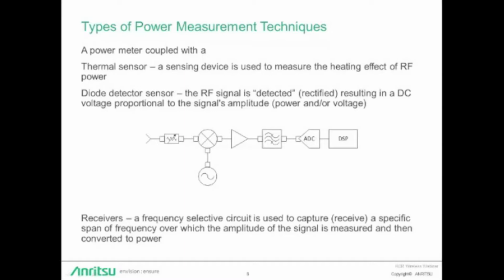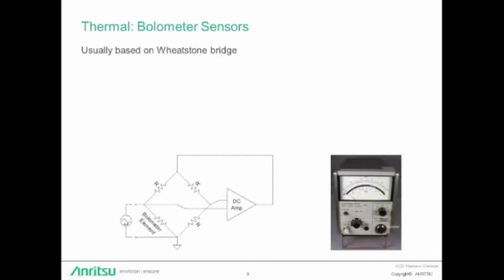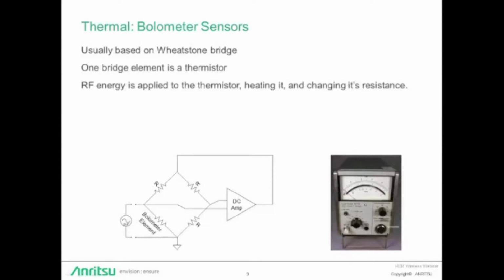So we're more interested in the first two, so let's look more closely at sensor-based measurement techniques. We'll start with the thermal sensors. There are two basic types of thermal sensors. One uses thermistors and the other uses thermocouples. Thermal sensors using thermistors are called bolometer sensors. Usually bolometer sensors are based on a Wheatstone bridge, seen in the diagram here, where one bridge element is a thermistor. When the RF energy is applied to the thermistor, its temperature changes, and so does its resistance. Circuitry adjusts the DC power delivered to the bridge to maintain balance.